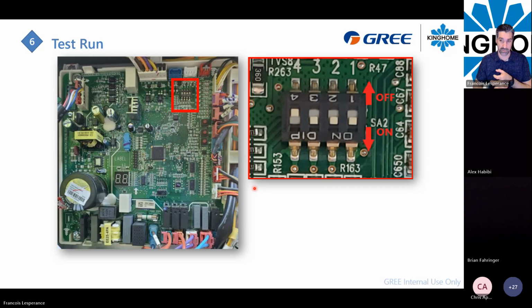you can force a defrost. By clicking the button right here, you will change a parameter that appears on the 2-digit display, and you can, for example, force a defrost, or force a cooling operation, or a recovery operation. In the case that you need to pump down the system because you have to work on the indoor unit, you can force the system to ignore the low pressure switch for a certain amount of time, and then you will be able to do a pump down properly, close your valve and shut off the power. This is what you can do with those buttons.